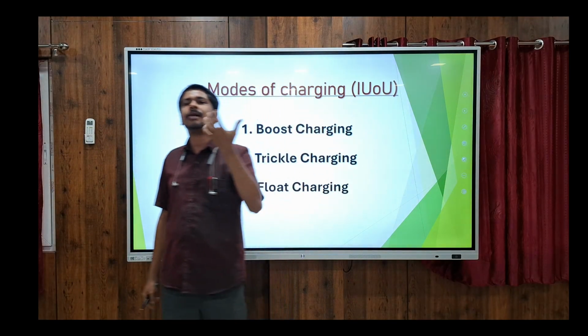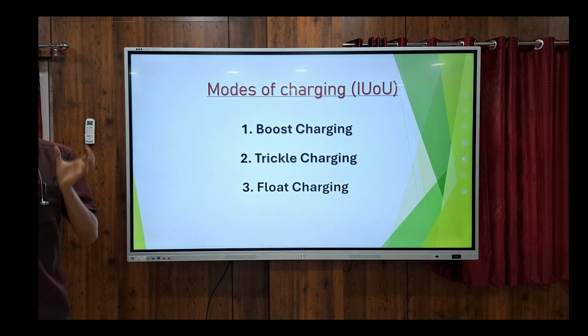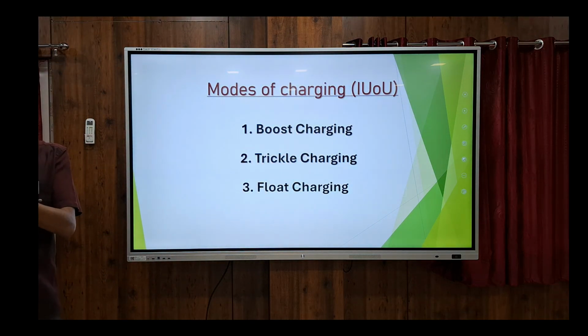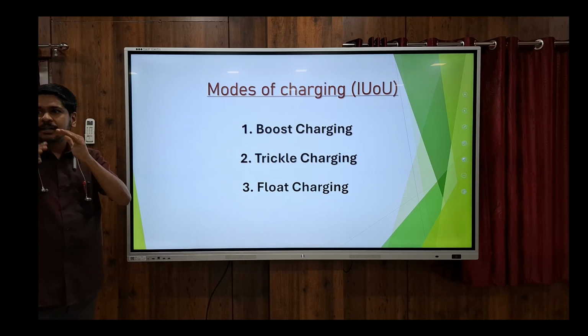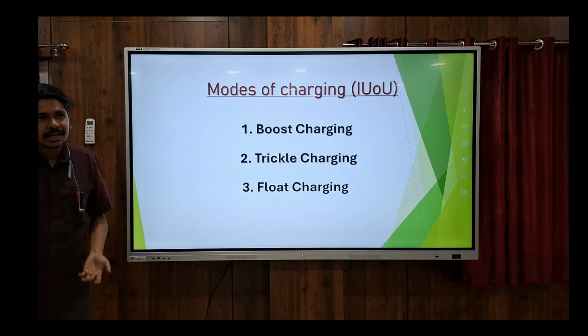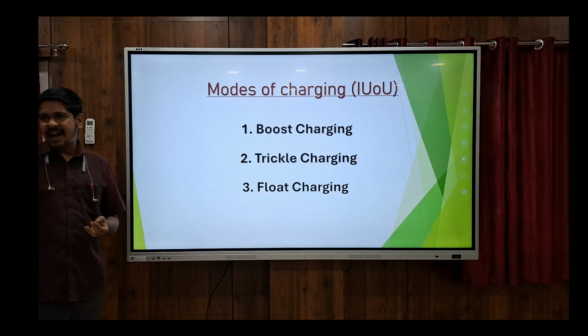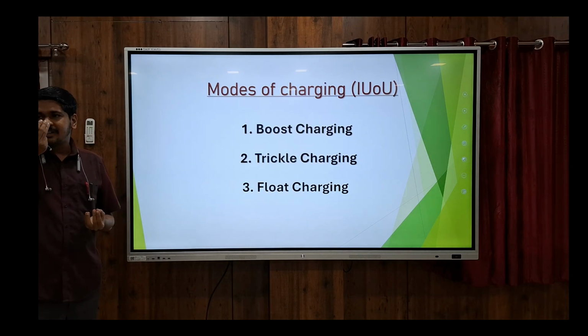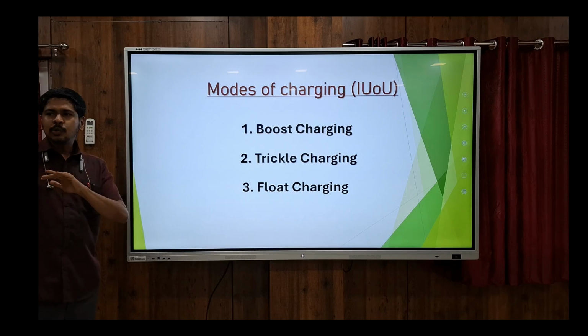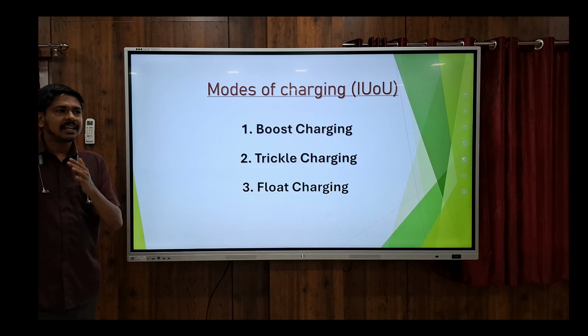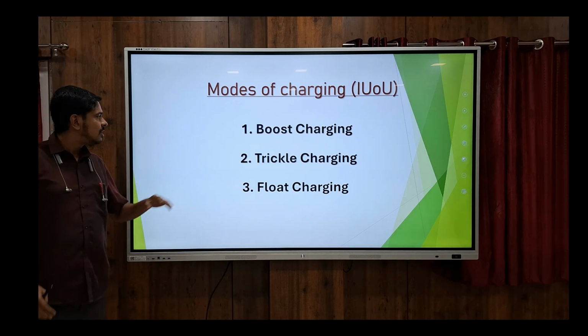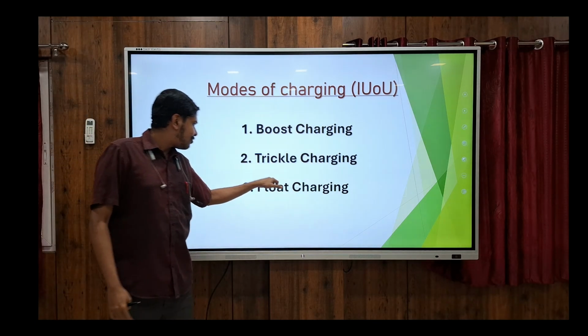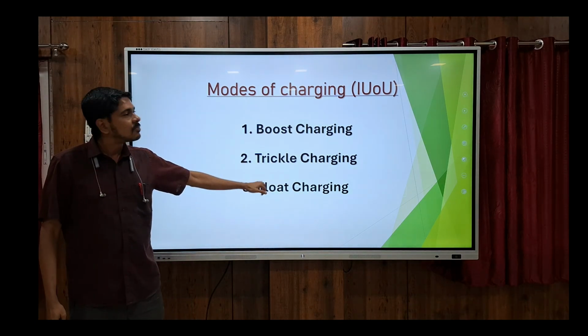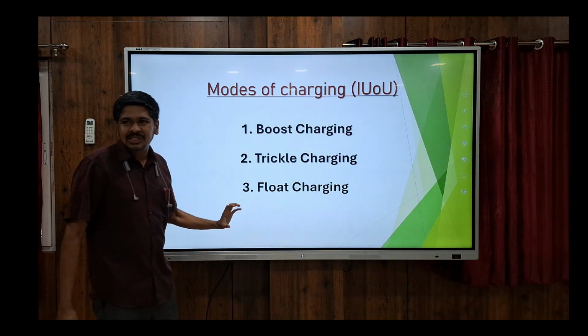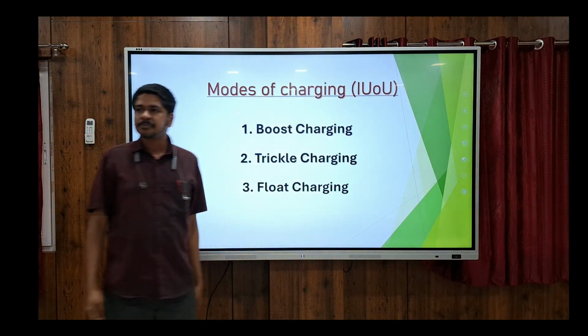U is the term used to denote voltage. In U0 mode, the voltage is kept constant, and as the terminal voltage of the battery slowly increases, the current consumed by the battery keeps reducing, until the state of charge reaches nearly 90 to 95%. This mode is called float charging, so U0 is almost equivalent to float charging mode.